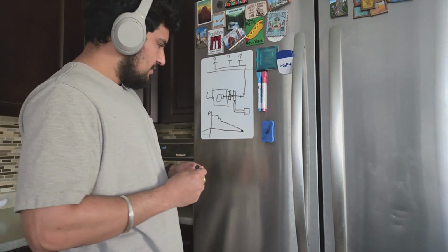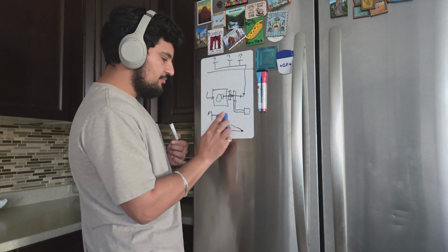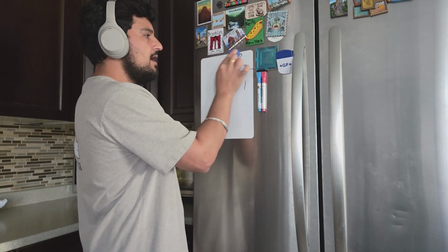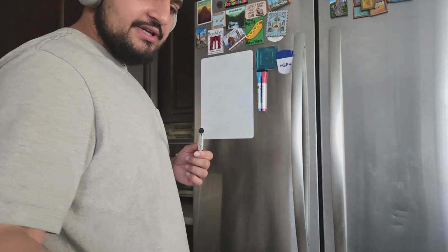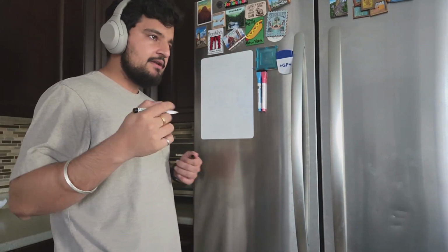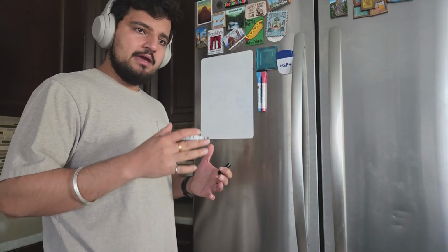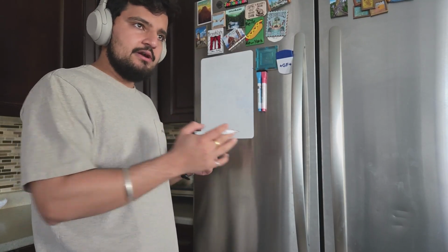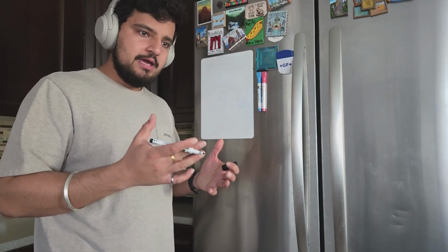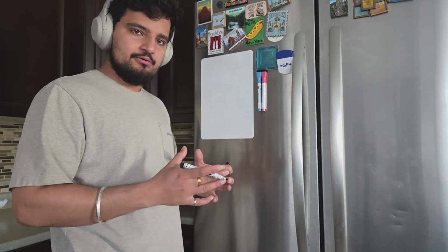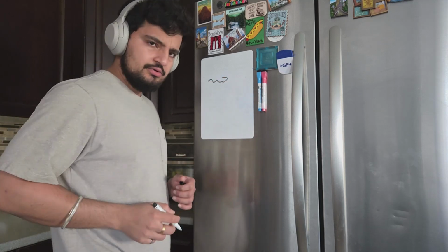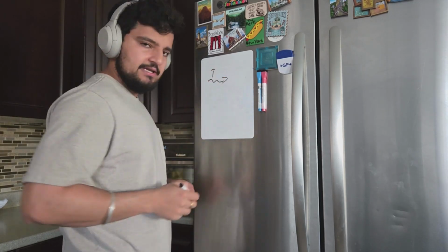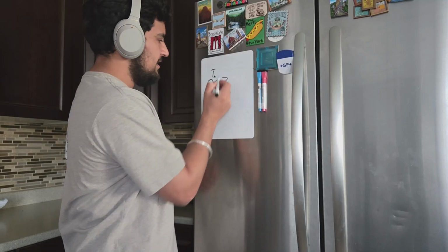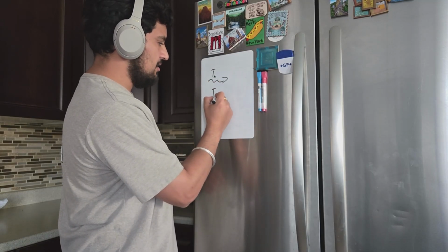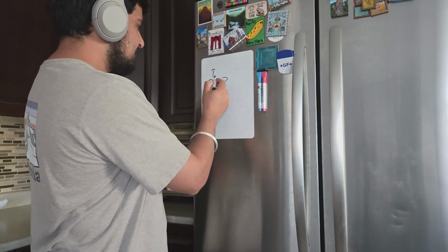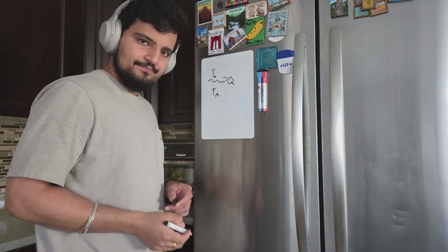So the fan has boosted the pressure just enough to push all that air through that pressure loss into your room. Now, let's talk about what could be the issue, right? So the original designer of your house has designed your air conditioning system so that all the heat loads that are in each individual room are covered by a certain temperature air at a certain airflow, right? So the air is going through into your room at some temperature T. So let's call this TA, and then your room has temperature TR, right? And let's say this air is flowing at some flow rate Q, right?